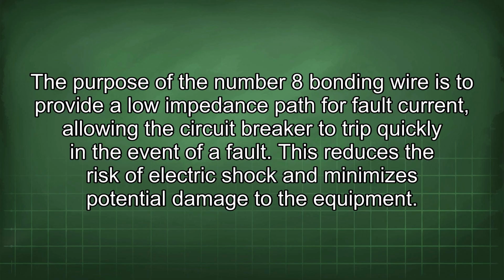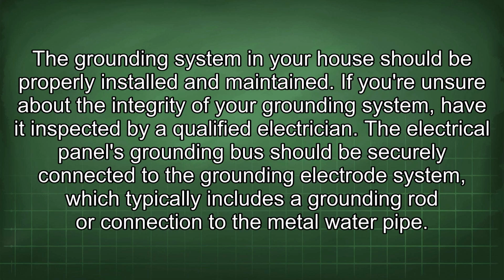The purpose of the number 8 bonding wire is to provide a low impedance path for fault current, allowing the circuit breaker to trip quickly in the event of a fault. This reduces the risk of electric shock and minimizes potential damage to the equipment. The grounding system in your house should be properly installed and maintained. If you are unsure about the integrity of your grounding system, have it inspected by a qualified electrician.